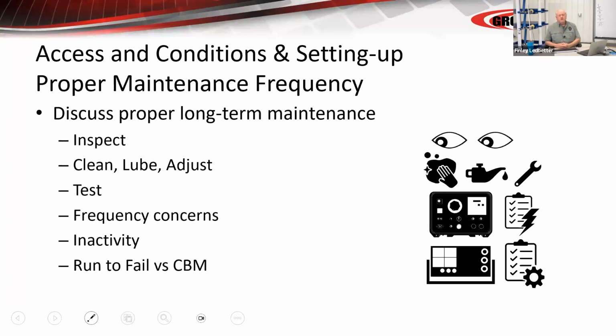The problem with that is we've done advanced aging studies on lubricants for EPRI and for other people, and we don't really have a good feeling about parting times and interrupting times on overcurrent trip devices, breakers, circuit breakers, oil breakers, when you get beyond probably about 5 years. And that's what the data shows. The data pretty much shows that if you take a circuit breaker and you close the contacts, you apply 1,000 to 2,000 foot-pounds of force, and then you wait 5 years, and then you ask the breaker to respond with the reaction time, parting time, speed, and velocity that it actually had minute 1, day 1, you're going to be disappointed.